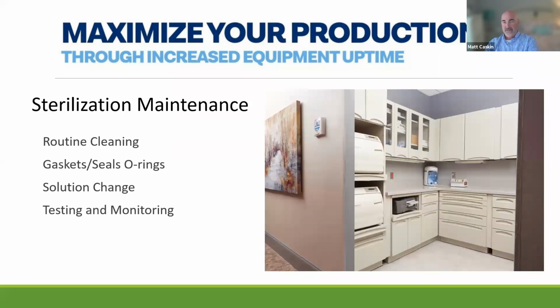Okay, again, routine cleaning: gaskets, seals, O-rings. Again, on the sterilizers that you saw previously, door gaskets, I can see a cassette sterilizer there in the picture. Those require changing out the seals inside. One of the ways you can tell when those start to fail, typically on the larger steam sterilizers you see on the left in the picture, is that they start dripping a little bit of water just underneath the door. You'll see a little pool of water, and you may even see some steam leaking out. On the cassette sterilizers, you'll definitely start to see some steam leaking.